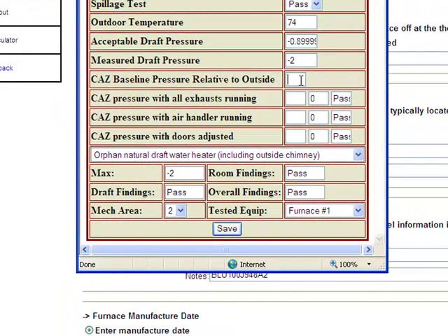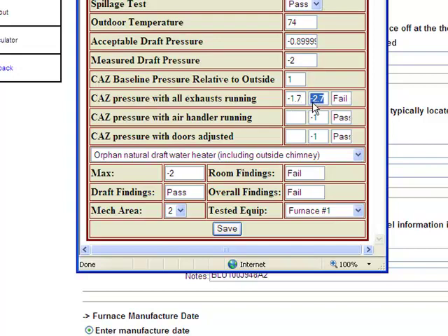There's a place to input your baseline pressure in the combustion appliance zone relative to outside, your pressure with all exhaust fans running, with your air handler running, and with your doors adjusted — the three different tests needed to determine the worst case scenario of your combustion appliance zone. This is where the math can get a little tricky for an energy auditor, as you may have a positive baseline number alongside a negative number, but the CAZ calculator does that math for you.